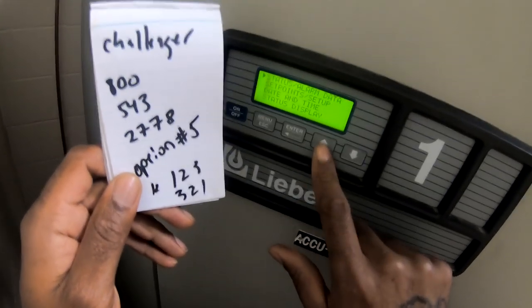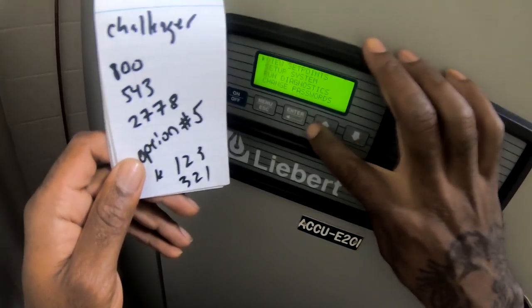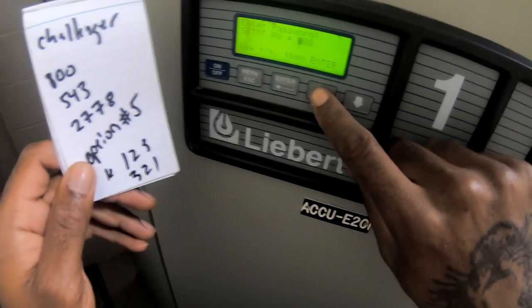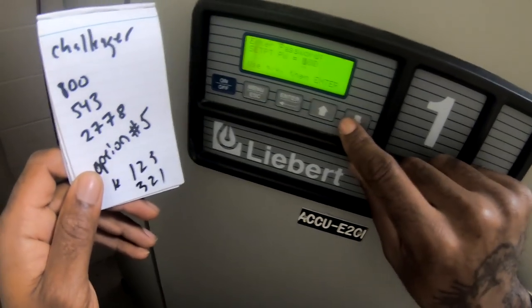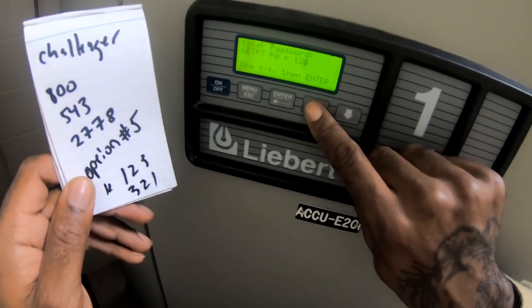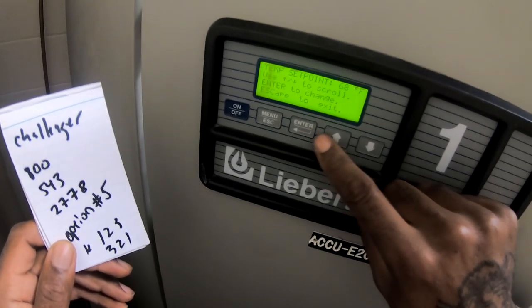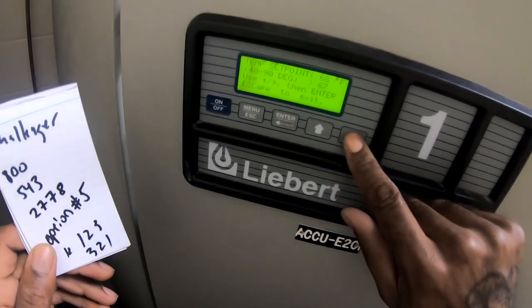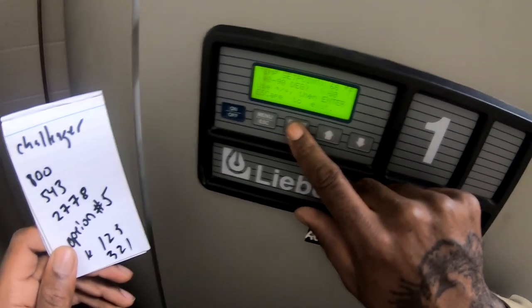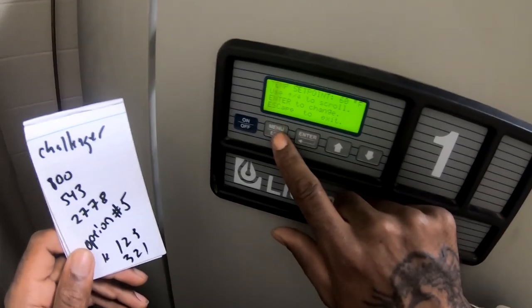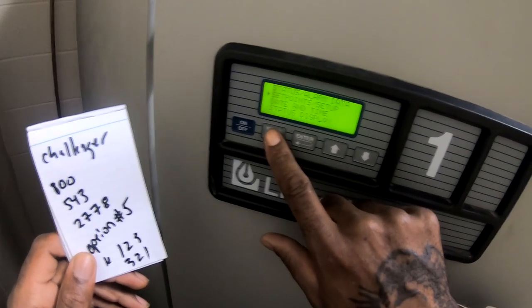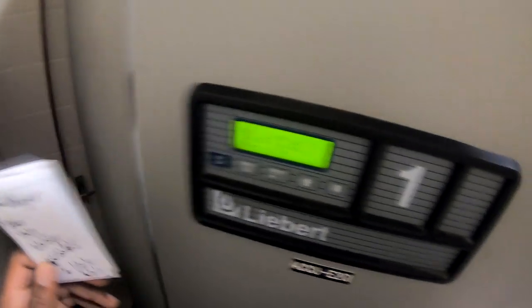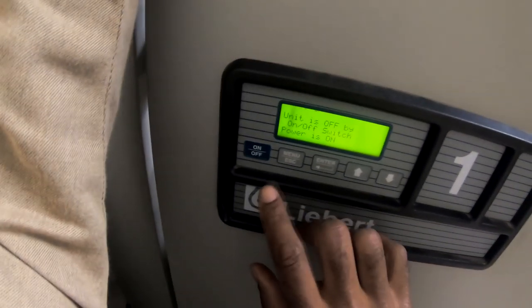Alright, so if you ever need the password to these style units to change the set point, the factory default is one two three, and for everything else it's three two one. We've got set points. View set point. We're gonna do enter to change set points, and the factory default is one, two, three. Alright, password okay. Enter, let's go to change, enter, and drop it down to 60. That's 60 right now. Enter, enter. Escape to exit. Power is on. Unit is off by on/off switch. Since I changed the set point, it should turn on. Give it a minute.